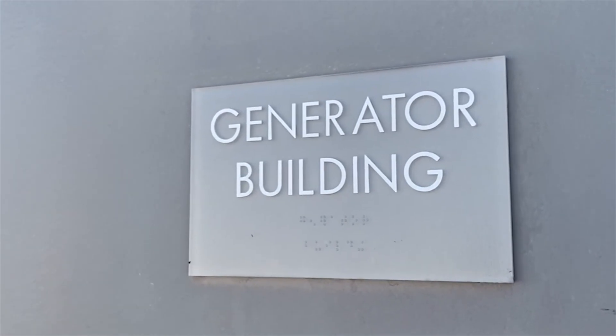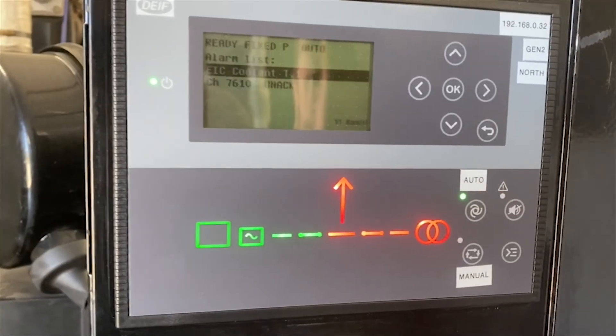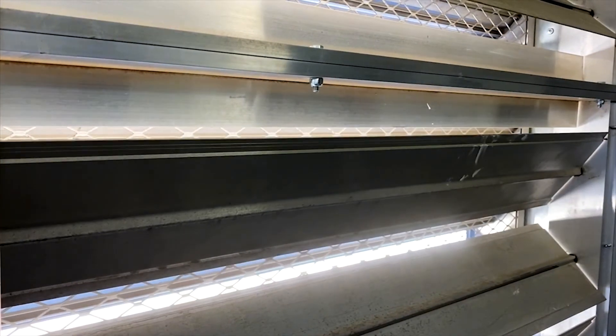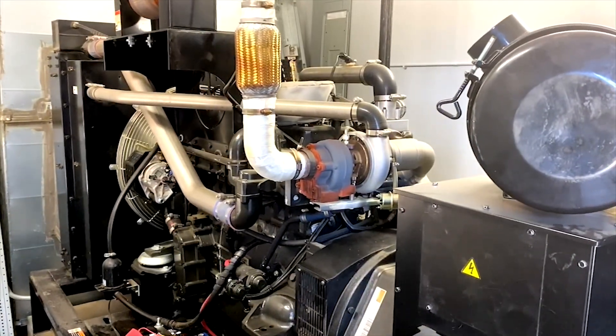When the batteries get to a low state of charge, to ensure reliable 24/7 power here, we'll send a start signal to the DEIF AGC150 genset controllers. That will charge these batteries back up to a full state of charge. We'll turn the generator off and then use the battery power until they get to a low state of charge again.